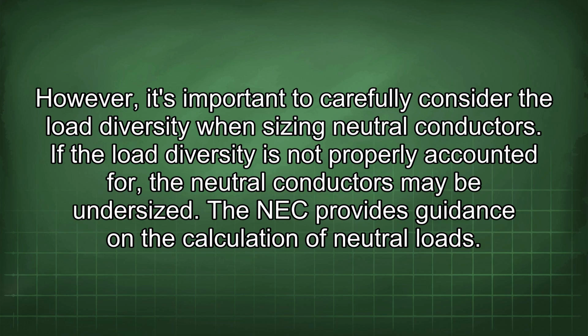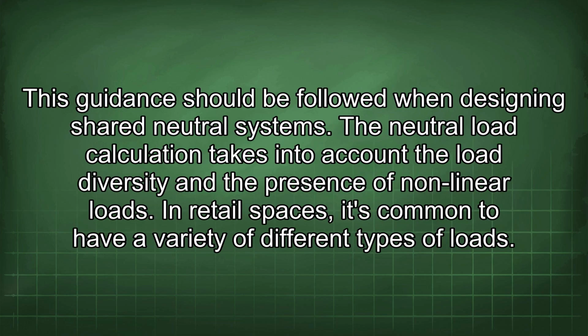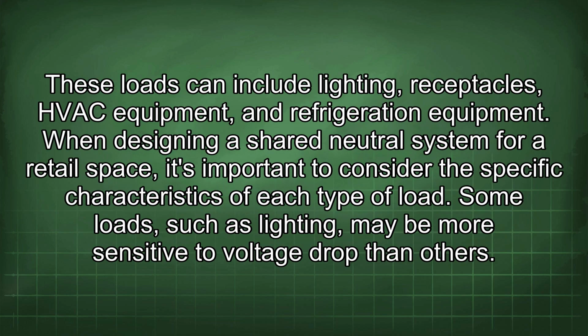The NEC provides guidance on the calculation of neutral loads. This guidance should be followed when designing shared neutral systems. The neutral load calculation takes into account the load diversity and the presence of nonlinear loads. In retail spaces, it's common to have a variety of different types of loads. These loads can include lighting, receptacles, HVAC equipment, and refrigeration equipment.